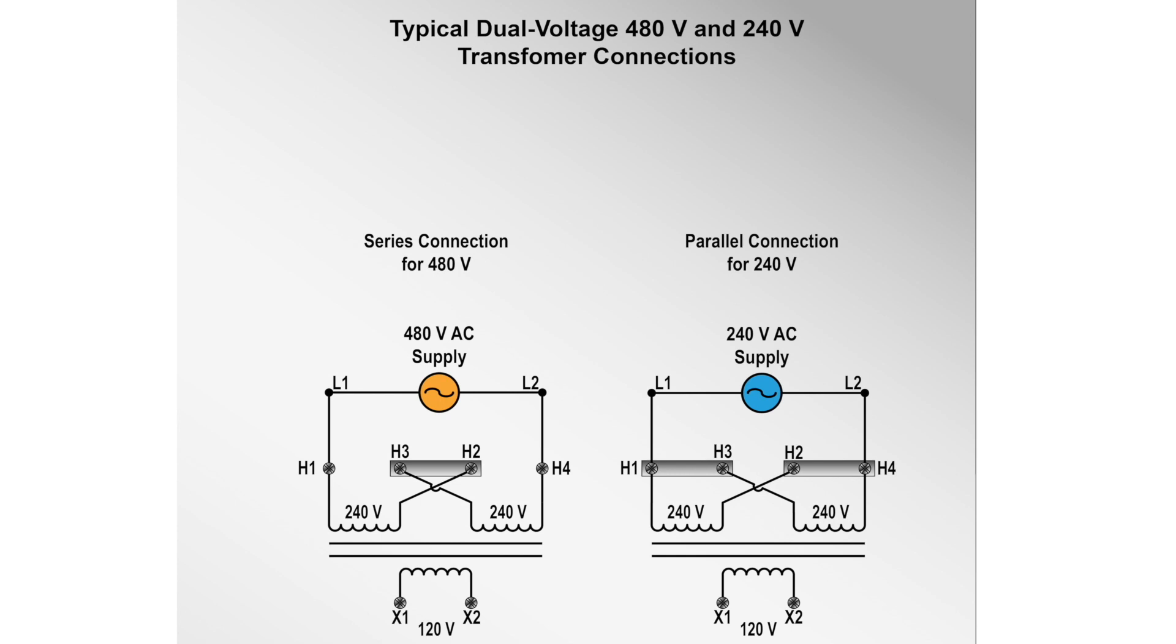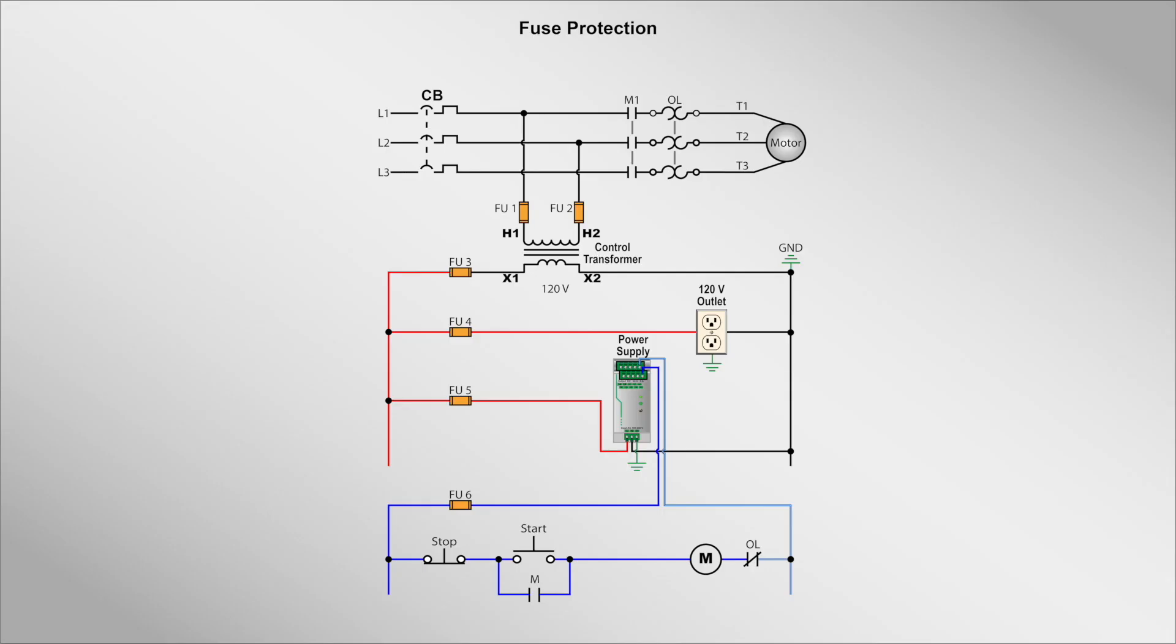In one of our earlier videos, we covered how to properly ground a transformer's secondary. The ground must be connected to X2 to ensure that an accidental ground in the control circuit will not start the motor or make the stop button inoperative. An additional requirement is that the transformer must be protected by fuses or circuit breakers.